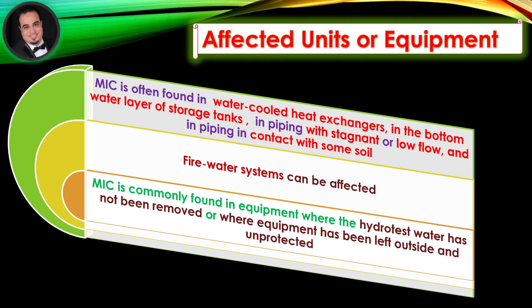Affected units or equipment. Microbiologically influenced corrosion is often found in water-cooled heat exchangers, in the bottom water layer of storage tanks, in piping with stagnant or low flow, and in piping in contact with some soil.